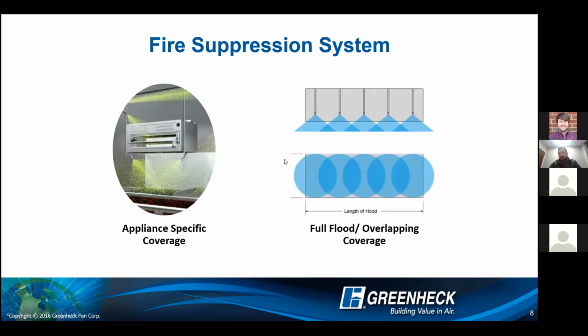Moving on from hoods, the second component of a KVS system is your fire suppression system. If it's a type 1 hood, it needs to have fire suppression. There are 2 types. It's going to be either appliance specific, standardly your Ansul R-102 system, or it's going to be your full flood or overlapping coverage. The big difference here is cost. The full flood overlapping coverage is going to be way more expensive than your appliance specific configuration.